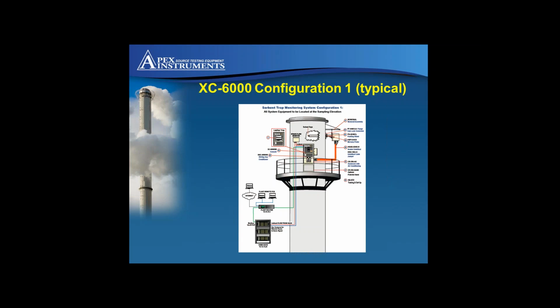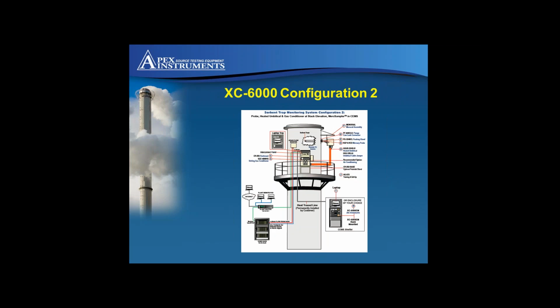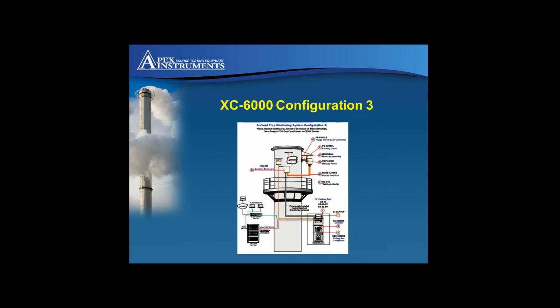Typically, we have 3 system configurations. Our most common installation is everything at the stack sampling location. A second configuration illustrates where space might be an issue, and just the probe and moisture removal are at the sampling location, with the control console down in the CEMS shack. And our third configuration is just the sampling probe at the sampling location, a heated junction box, and a heated sample line, bringing the gas down to the CEMS shack prior to conditioning and volumetric measurement.